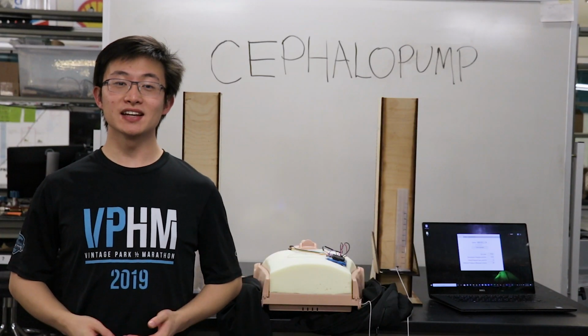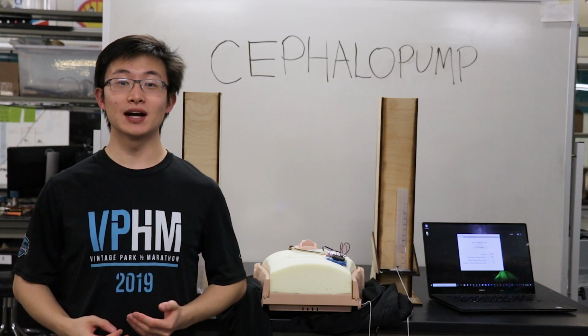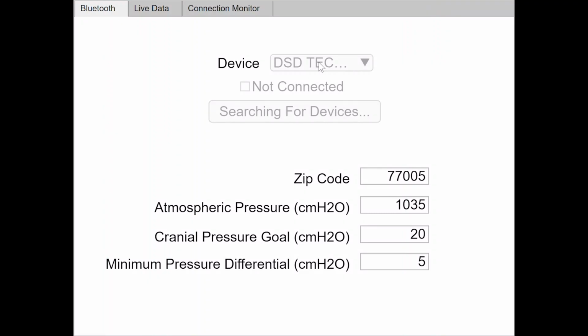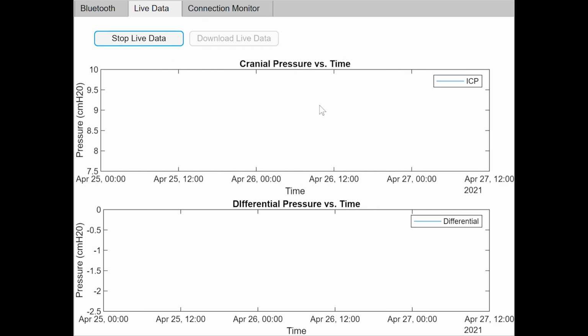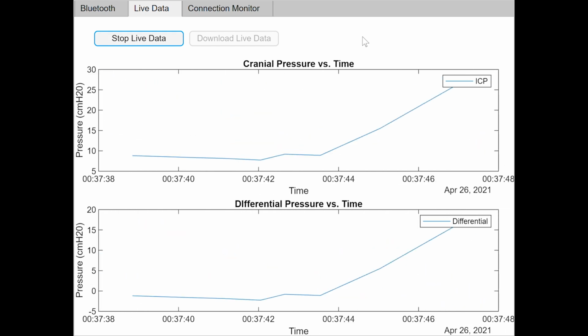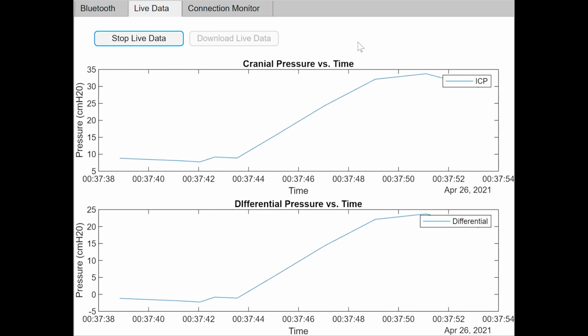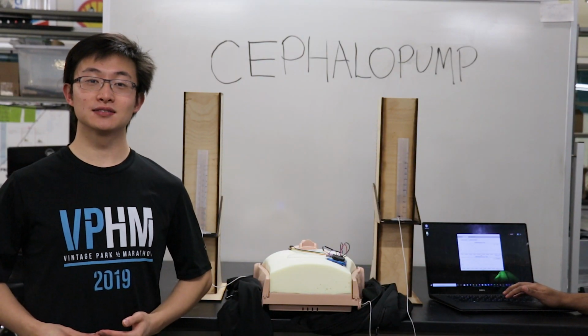Once implanted, the Cephalopump can be connected to another device over Bluetooth using our Brain Drain application. To start the app connection, select the device in the Bluetooth drop-down menu. The application will allow the user to change pressure parameters in order to best address the patient needs. In the Live Data tab, the user can read live pressure data sent from the device. Finally, when the user is done reading live data, they can also save the data to their device.